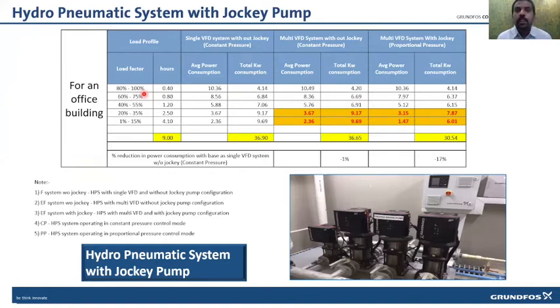We all know when we use a hydro booster system, we size it as two working one standby, or three working one standby, of the same capacity. That is okay for a full load. But most of the time we operate at part load, let it be a residential, commercial or IT building. Our variable loads will be more, and peak loads and lean loads will switch over here and there. So when we operate a bigger pump for 20 or 30 or 40% of load, it drops its efficiency. So we need to maintain a higher efficiency even at part load.